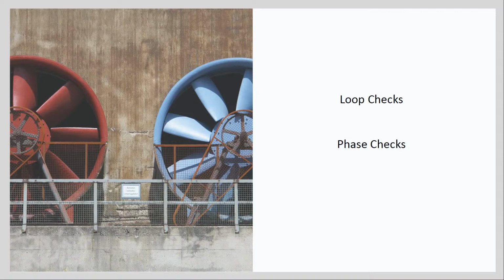So then you may move on to primary and secondary injections of the CTs and PTs to test some of the relays. Secondary injections can be applied to prove the operation of the relay at one or more settings values. As well, you can do primary injections to prove the stability for external faults and to determine effective current settings for internal faults. You can also use primary and secondary injections to test some of the protection scheme logic to ensure that alarm set points are responding correctly, that the system is logging alarms, and test that the logic is reacting correctly based on the faults that are being detected.